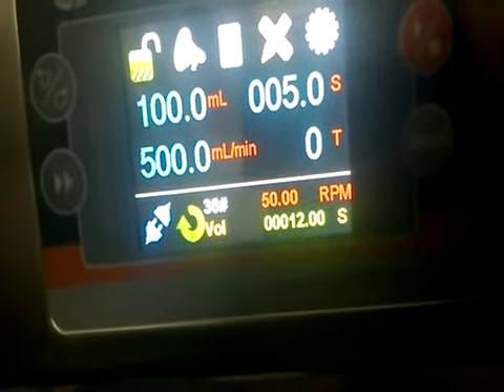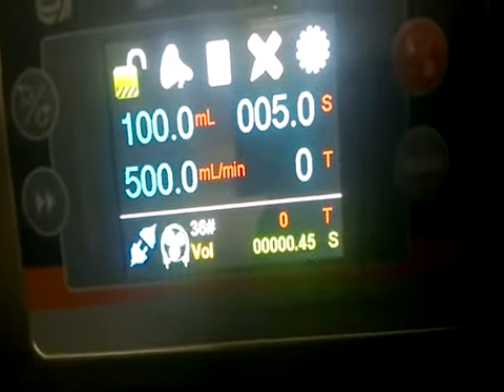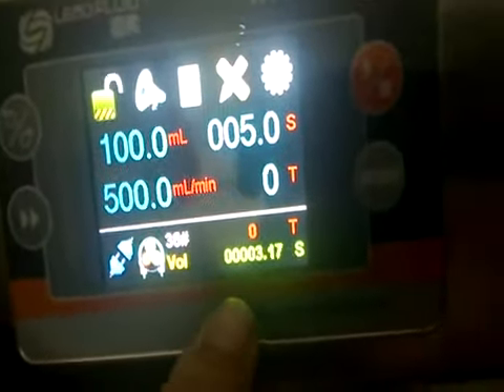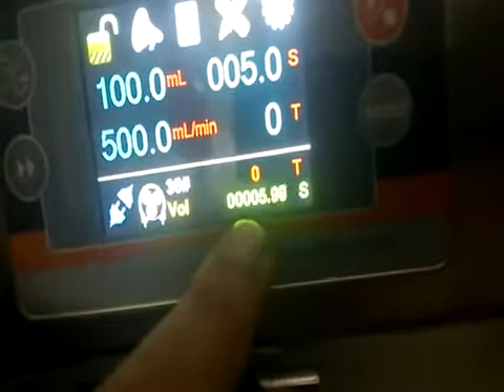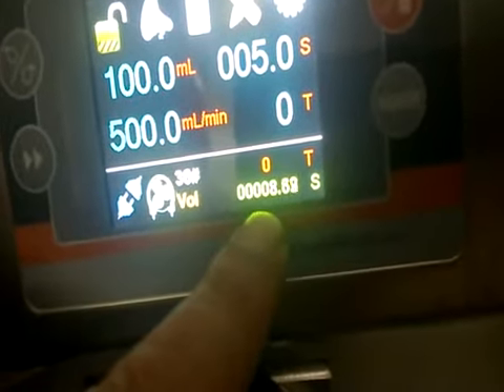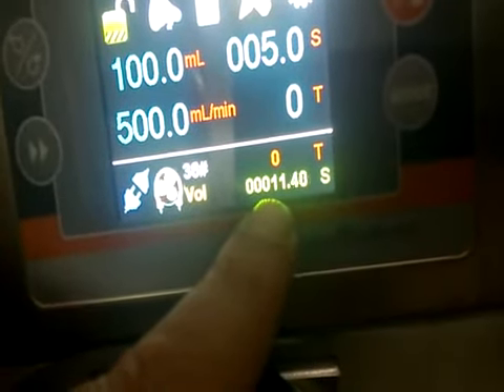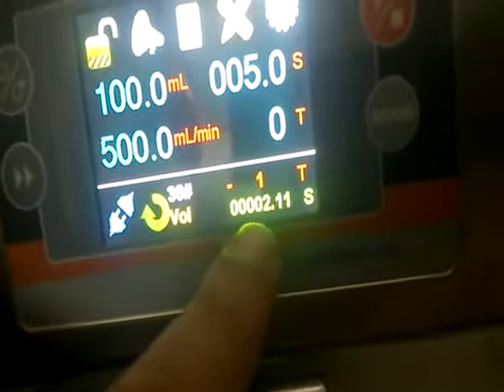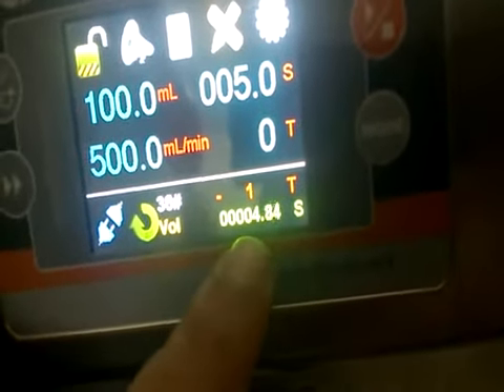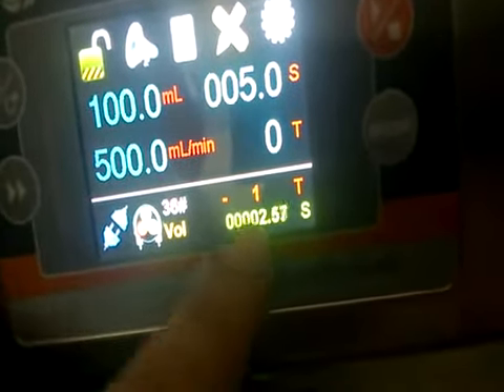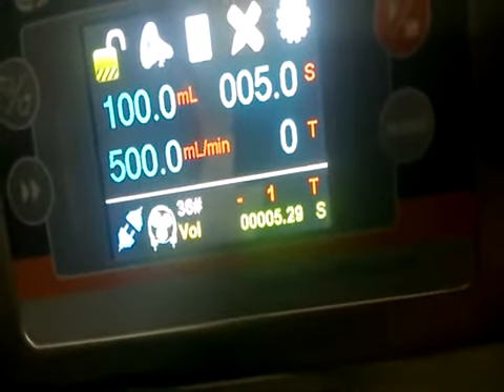I've set all these functions and I will say start. What it will do, it will run for the time till it fills 100 ml. So maybe 12 seconds. Then it will wait for 5 seconds. Now the pump is stopped for 5 seconds. And now again it will run for 12 seconds so that 100 ml is dispensed. So it's a nice function. You can see that the volume is coming, then it stops. Okay, I'm stopping it.